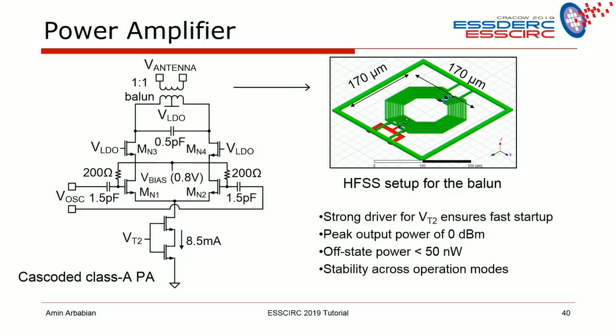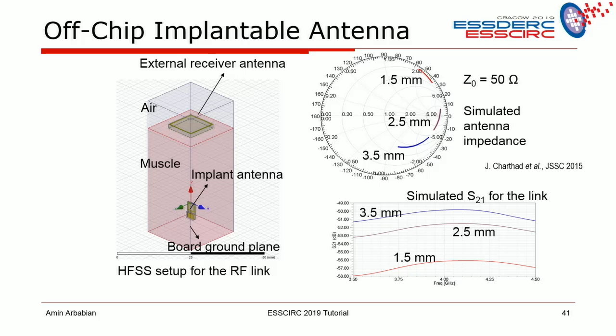into the transmitter. And if you can see here, the peak is pretty high, substantial, and the reason we needed a high-power PA is that the RF link is very inefficient. It's the whole purpose we went to ultrasound. And so for the uplink, we really need to push the envelope on how much power we put into the transmitter. We also optimized the transmitter coil for a specific scenario, for alignment, and for about 2-3 centimeters depth. So these are the different impedances and different coil sizes. This is the whole chip with the power breakdown.